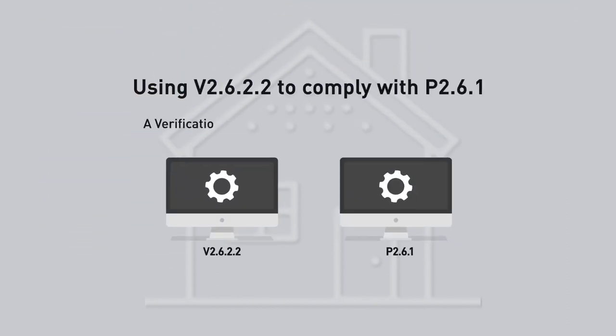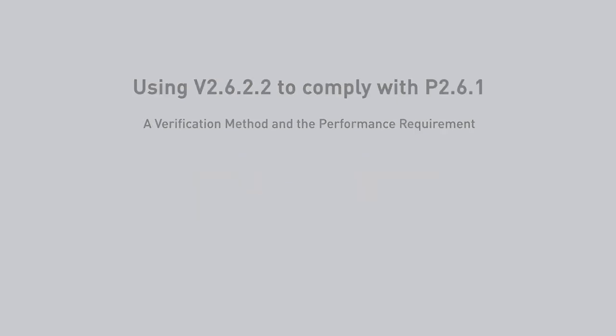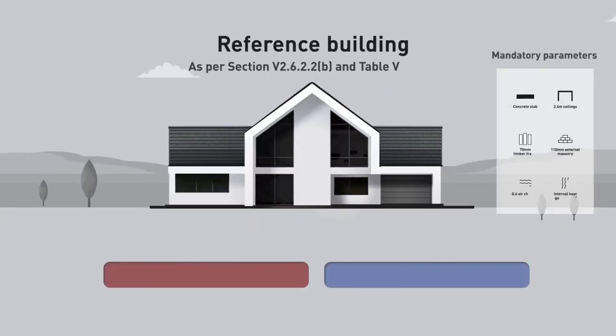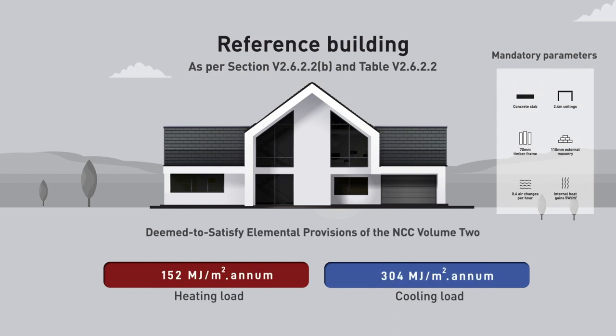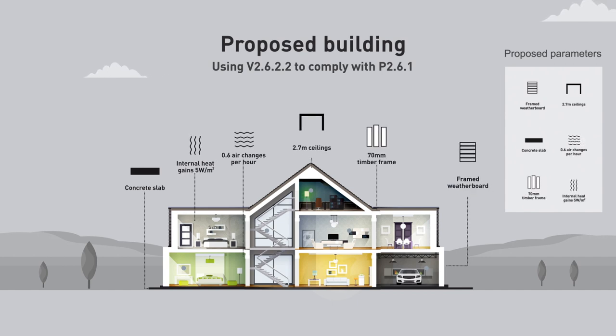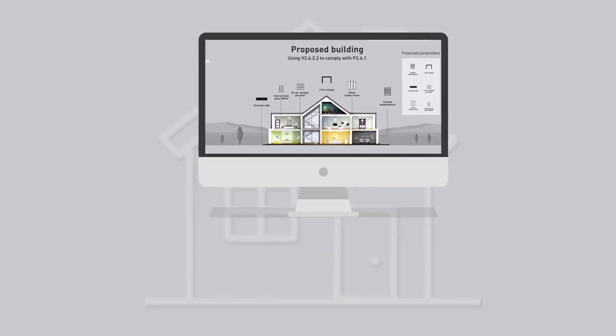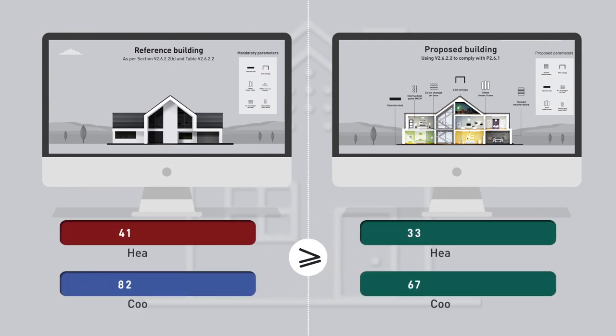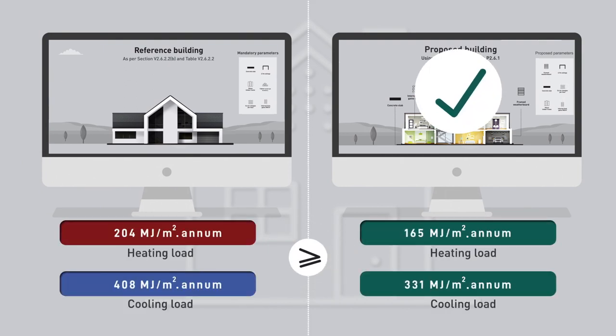This method involves using software to perform two modelling runs. The first models the building complying with the minimum deemed to satisfy provisions of NCC Volume 2 — this is the reference building model providing the cooling or heating load targets. The second run models the building using the actual design elements proposed, remembering that these still need to comply with the NCC requirements for insulation, thermal breaks and building sealing. Heating and or cooling loads are calculated for each model, and if the proposed building loads equal or are less than that of the reference building, then it complies with the requirements.